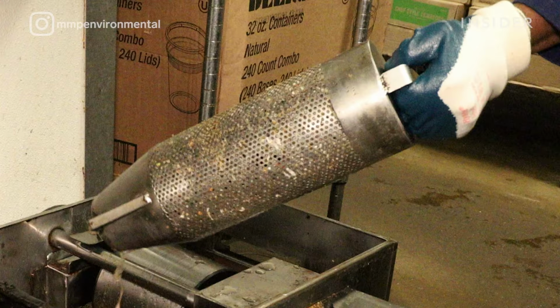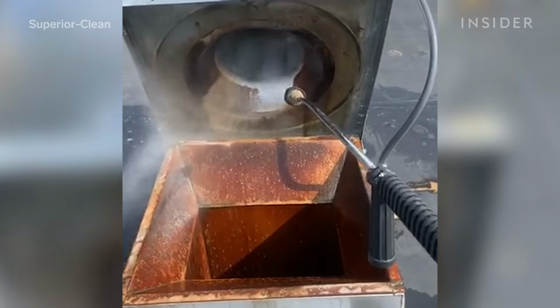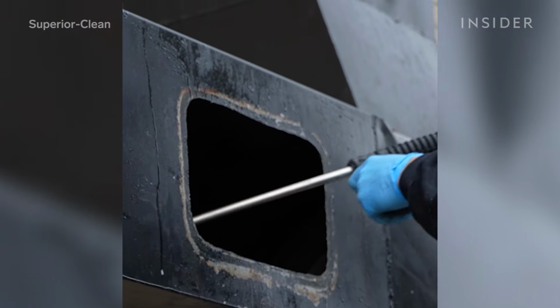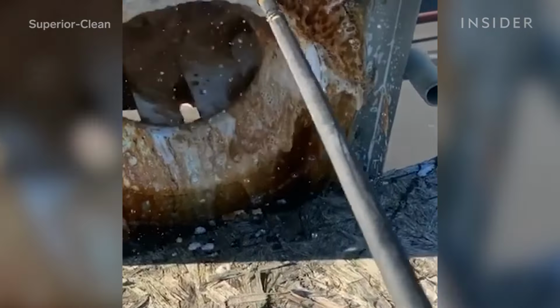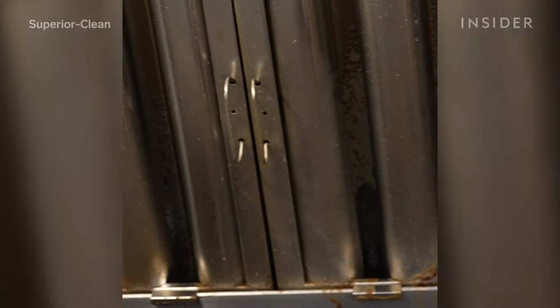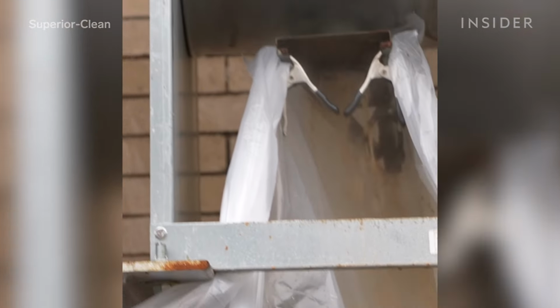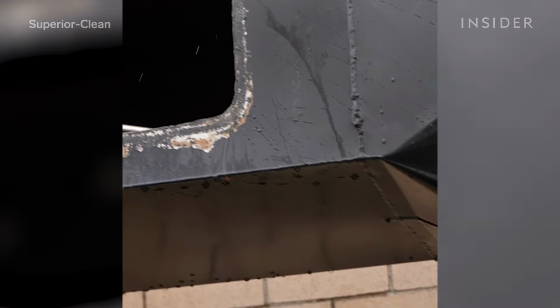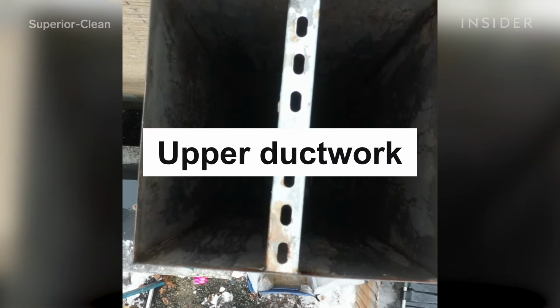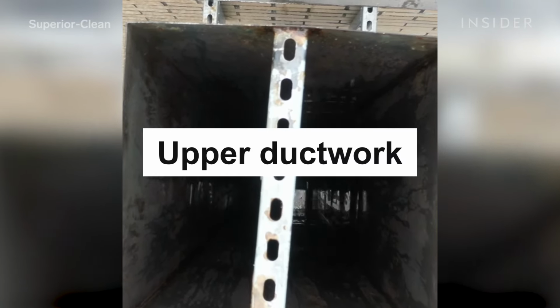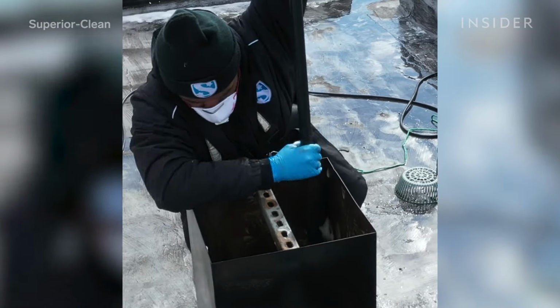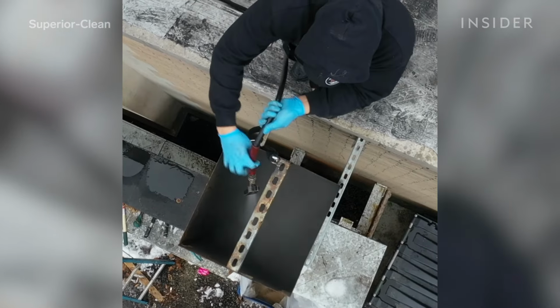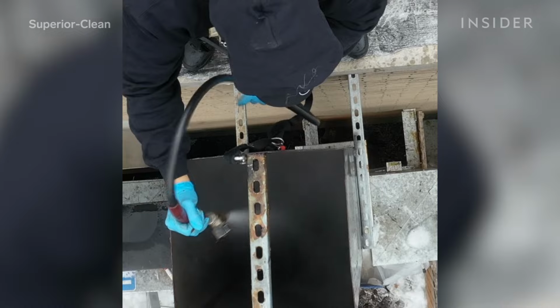Steve, the owner of Superior Clean, walks us through how he cleans a commercial exhaust system. We begin the cleaning process by removing the kitchen hood filters and wrapping the exhaust hood to ensure that we properly contain all of the greasy water. We'll start at the upper ductwork where the grease accumulates the most. The top of the ductwork here is where the grease, the smoke, and the heat exits.